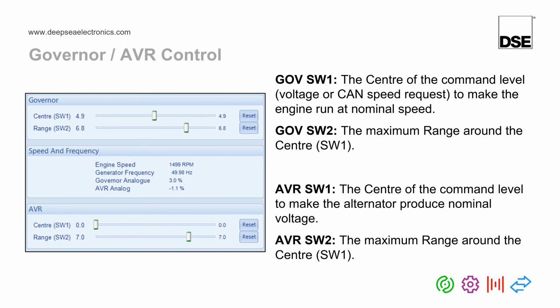I've told you that the maximum current would be 20 milliamps. You could then measure the resistance of the cable and therefore work out what the voltage drop across that cable would be. And in most cases, as the resistance of the cable is very small, and the maximum current that the DeepSea module would ever produce out of its governor or AVR output is 20 milliamps, also very small, then the voltage drop you would see across that cable should, in theory, be very small.